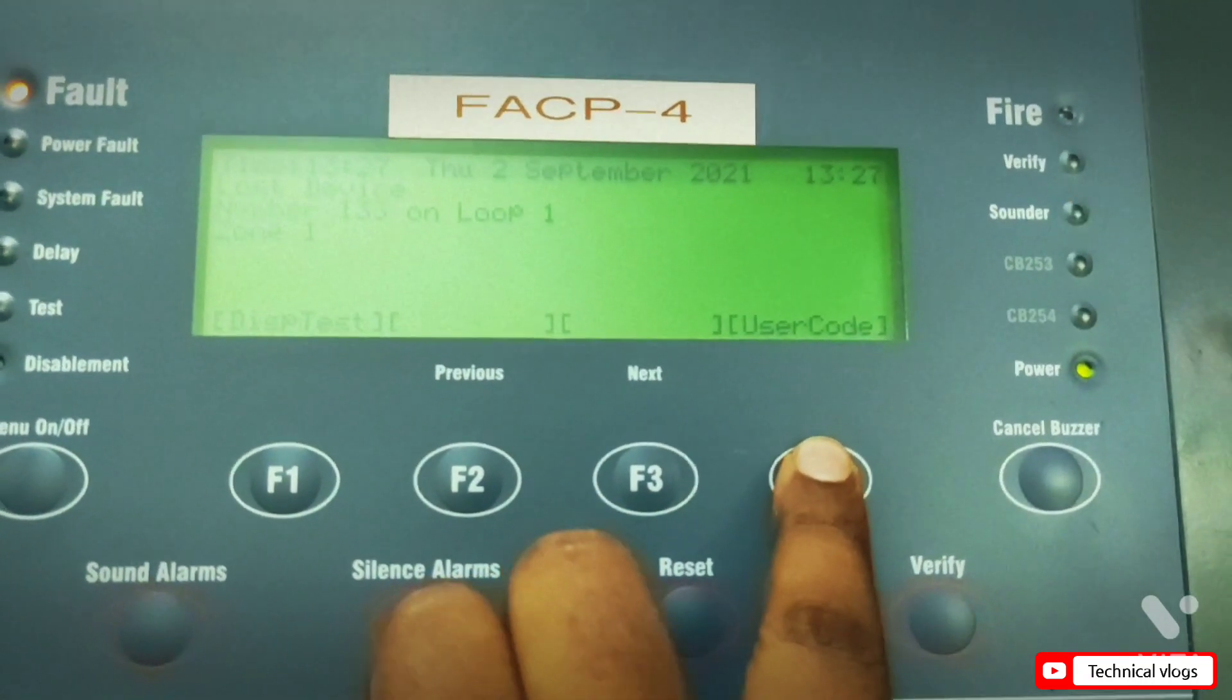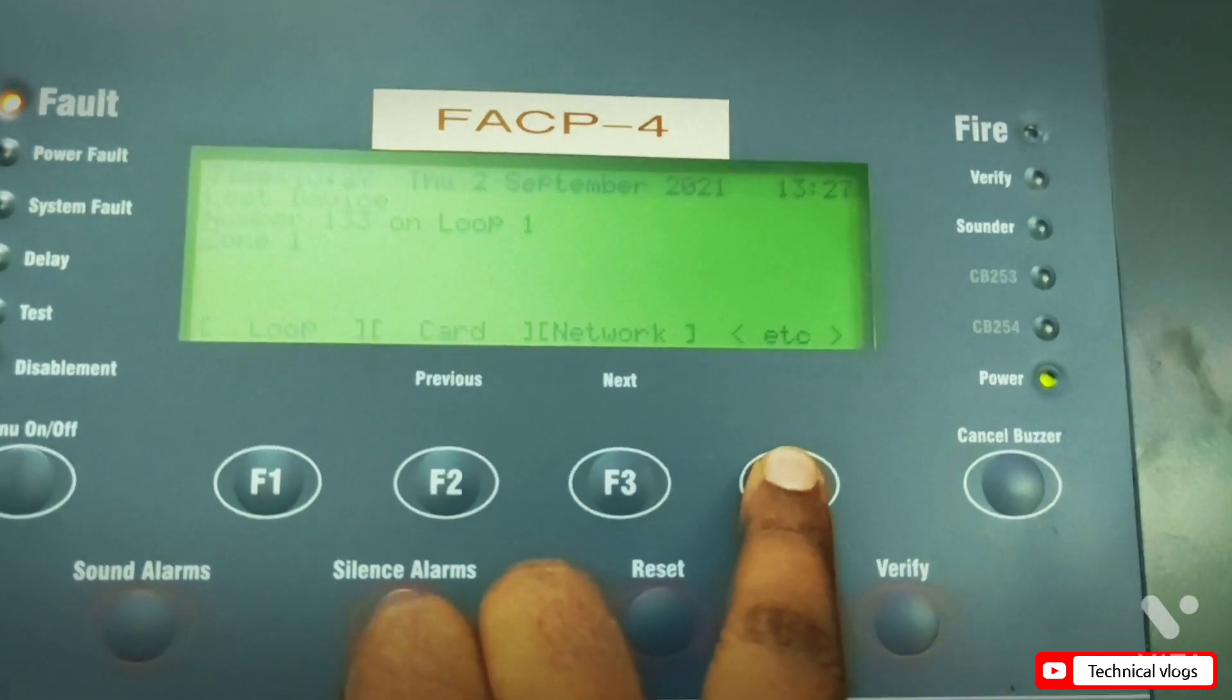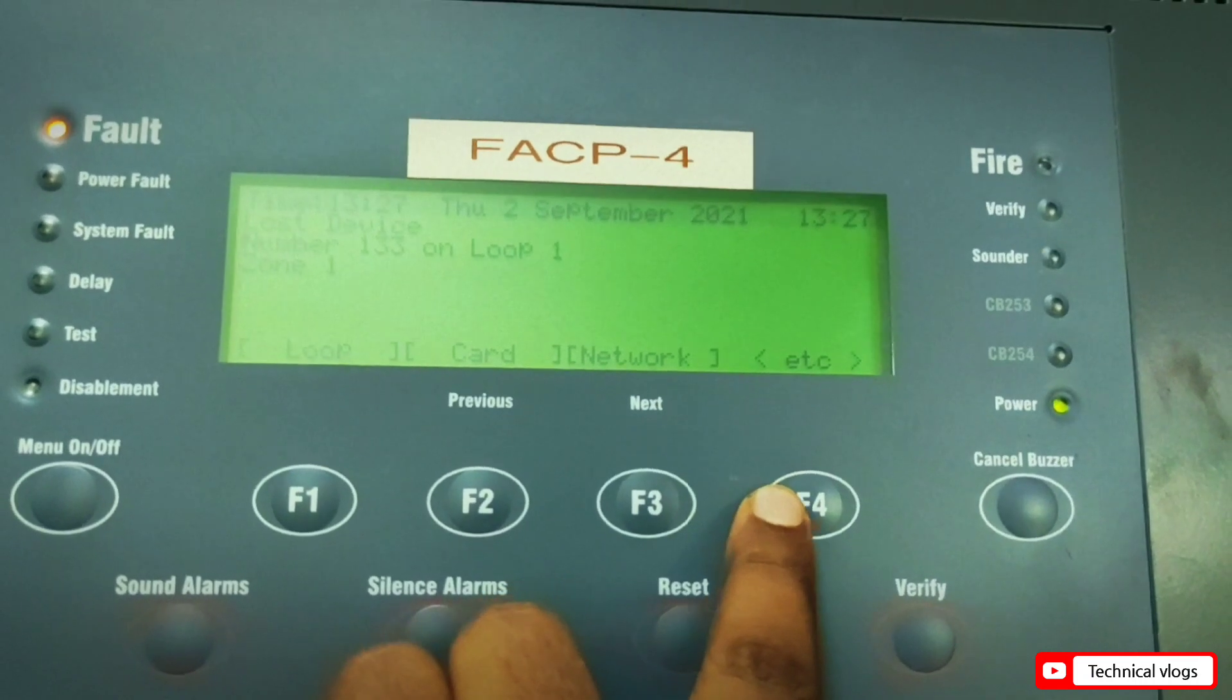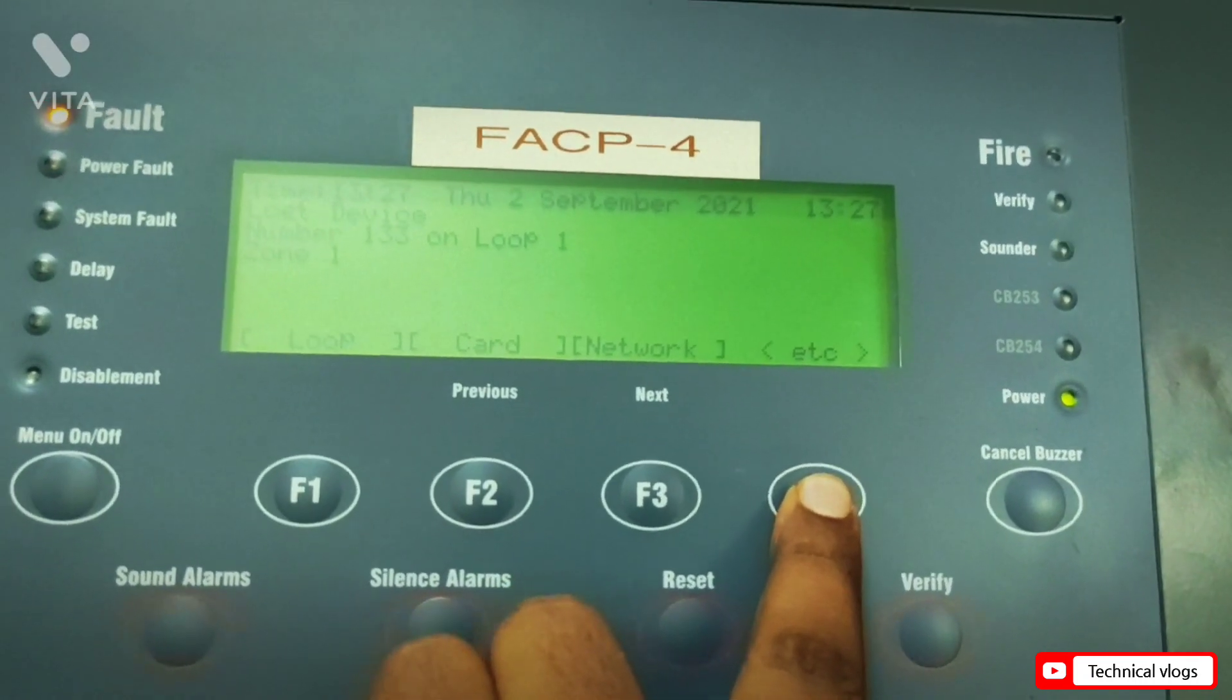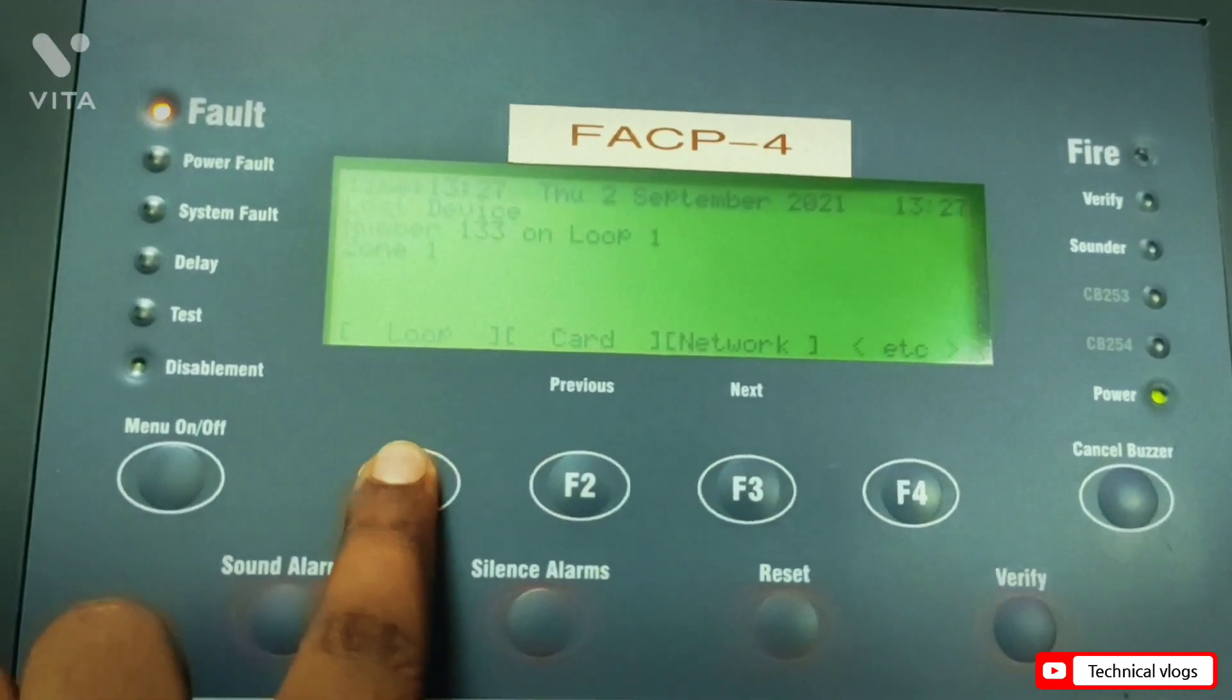This function in Gents Vigilon is very useful for preventative maintenance. Using this function, we can easily find cleanable dirty smoke detectors and replaceable dirty smoke detectors.